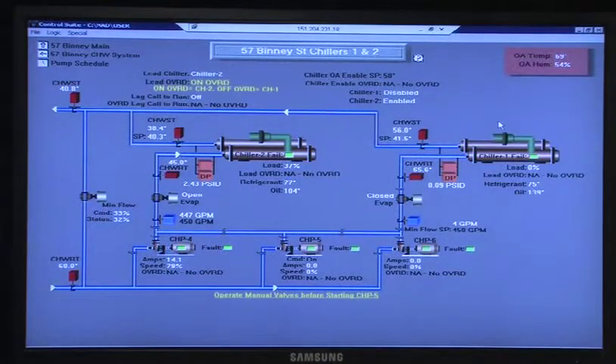One of the things I see on the graphic is on the condenser loop, it shows everything on the right side, and on the evaporator loop, it shows on the left side. But the bundles, the way they're on the machines, they flow through the machine, they don't go out the same way. They go this way and then back out.